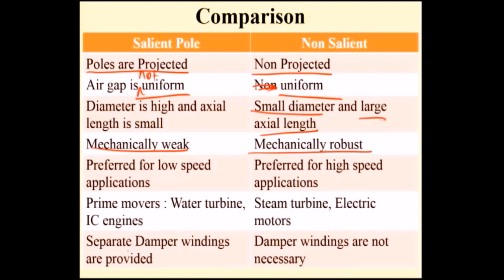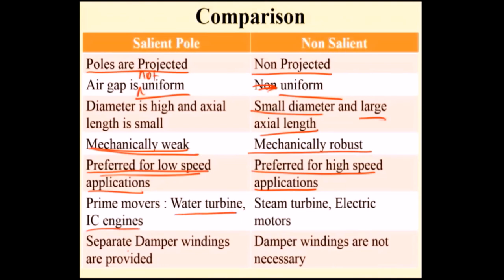The non-salient pole rotor is mechanically robust. The salient pole rotor is suitable for low speed applications, while the non-salient pole rotor is suitable for high speed applications. For low speed, water turbines and IC engines are the suitable prime movers. For high speed non-salient pole rotors, steam turbines and electric motors are the suitable prime movers. Damper windings are required in the salient pole rotor but are not necessary in the non-salient pole rotor.